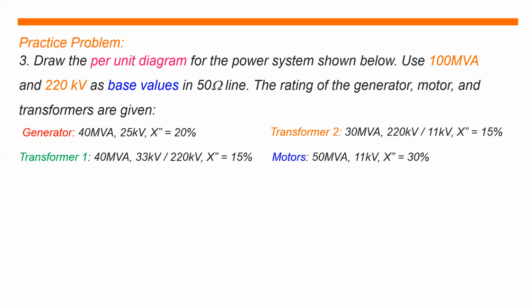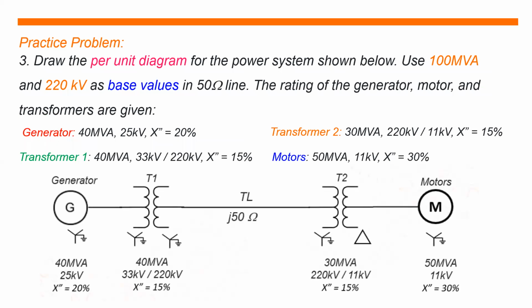Practice problem number 3, draw the per unit diagram for the power system shown below. Use 100 MVA and 220 kilovolt as base values in 50 ohms line. The rating of the generator, motor, and transformers are given. So we have here generator, rating ay 40 MVA, 25 kV. The reactance is equals to 20%.